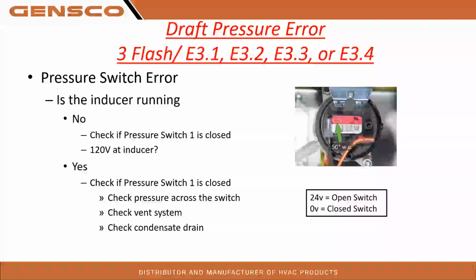So it could be a pre-check error, right? Knowing the sequence of operation, we're going to send voltage down those safety circuits, rollouts, limits, pressure switches, just make sure that they're all closed if it's a safety series, right? And then we're going to make sure that the pressure switches are open because we can't see voltage coming back, right? So we're going to send voltage out. It doesn't come back. We know that switch is open. So if the switch is closed, then all of a sudden we see a callback and we'll never turn the inducer motor on, right? Because we know that that switch is in a position it shouldn't be in, right?